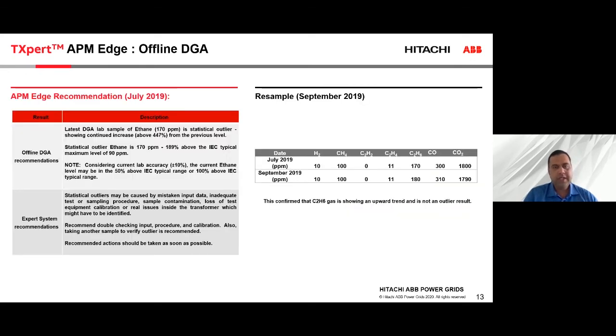So in July 2019, as soon as we uploaded this data, our offline DGA recommendation straight away recommended that the last data point is a statistical outlier because it showed an increase of more than 447% from the previous level. And we also said that, considering the lab accuracy, the gas is 50% over the typical IEC range. And the expert system automatically recommended that statistical outliers are usually caused by either data corruption or the sampling procedure being wrong, or the sample being contaminated.